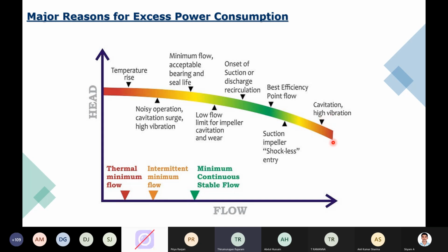Because here you find when you are operating close to, I can say, the right hand side or the end of the curve situation, your NPSH will be higher and the energy consumption of that particular pump will be much higher. So everything will be in a stressed situation, in which it will initially cavitate because your NPSH required will be very, very high, and in turn it is not able to suck the water out very easily, and that will have an impact on vibrations, and obviously that impacts all your rotating parts, mechanical seal, your bearings and other parts in it. So that will seriously have an impact on the pump performance.